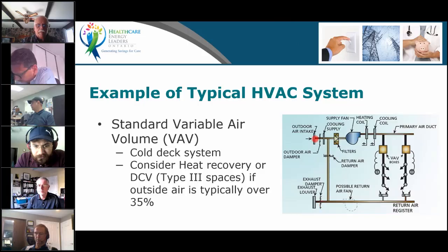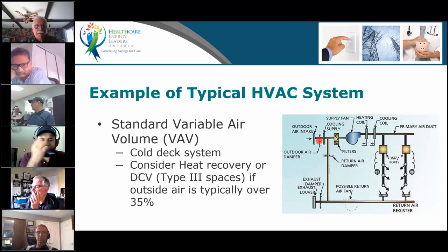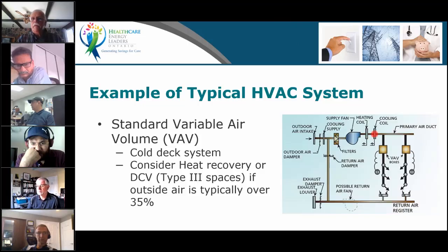So even if you have a heat recovery wheel right here, it will not kick in because your mixed air is already warm enough. Now, for any of you that have a heat recovery chiller, you could decide to put a heat recovery wheel here. You will overheat your mixed air. You'll use your cooling coil to recool that air, and that will transfer heat to your condenser that will then serve to heat your building. So that's why I say you need to know how your systems work to see if a measure is appropriate for your system. In this instance, DCV and heat recovery, and DCV is demand control ventilation, would be something you would have to look at twice before installing.